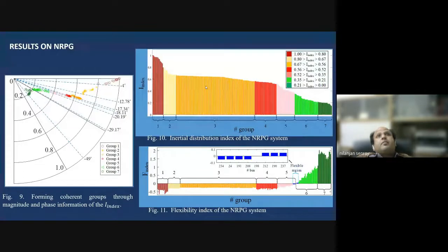So in large systems, for instance, these simulations were done with the Northern Regional Power Grid. In large systems with a large number of generators, it is possible to identify some key modes. And based on those key electromechanical modes, you can form groups of generators. These groups of generators are called coherent groups, and each group would have very similar dynamic characteristics. So instead of specifying these indices for different buses, you can specify them for different groups. You can see here on the right, top right and the bottom right, the two graphs show that for groups of generators, the indices are almost the same. And so rather than computing this index for all the generators, you can compute this index for groups of generators.